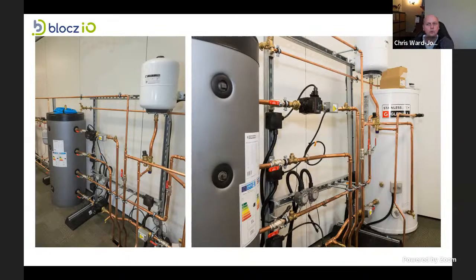We actually condensed all of this down into a single rack. So whilst it looks quite big right now, it's purely so people can see it and see how it works. What we have, effectively, is a thermal store. We've got some variable speed pumps on the other side of this pipework, the flow and return from those heat exchangers we saw previously. And there's another heat exchanger on this side, outside of the racks of this heat recovery system.